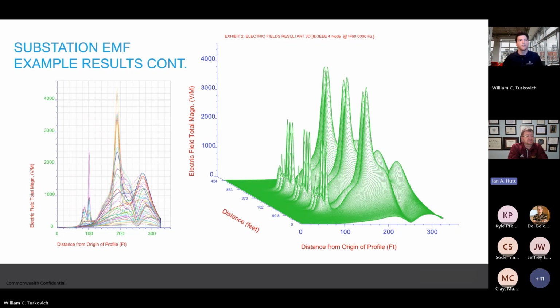One thing to note too, as we do more of the renewable collector stations - which could be BESS, solar, or wind - once you generally have an underground medium voltage network connecting to an array of solar PV and inverters, wind towers, or a battery yard, those underground cables come up and into your breakers. We actually see a fairly large impact from those cable risers on the EMF side. So whenever you have a station that's tight with a very limited fence, there may be potential EMF concerns that are unexpected when we talk about those cable risers. Just a neat piece of information to glean from this, and something from our experience that's worth noting.